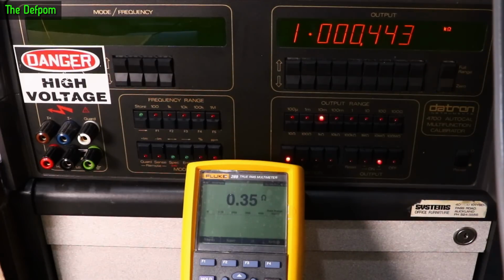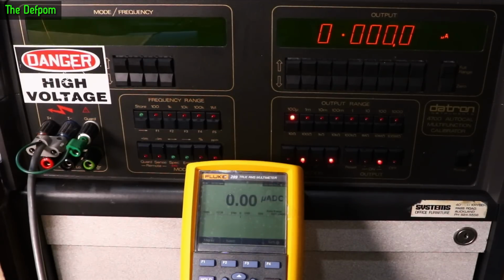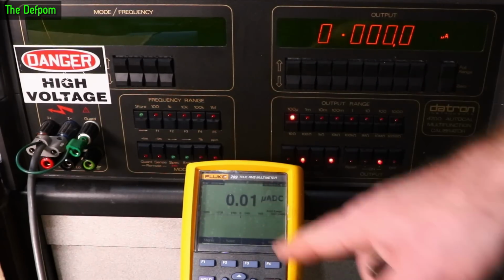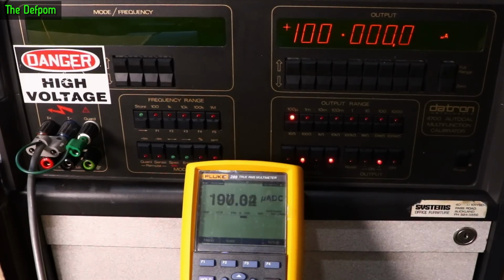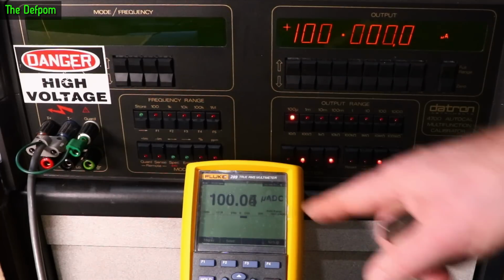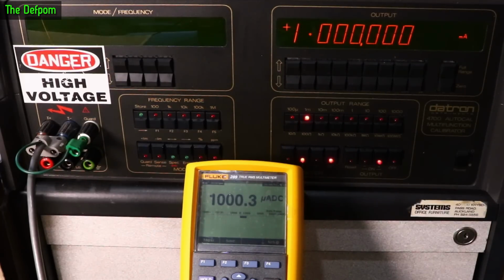And I've got a short here is 0.175, and that's 0.35. So it's very slightly better than this calibrator does for a short. Not much in it though. It's all good. Now let's do microamps DC. Got the output 0. We're getting 0. Still 100 microamps. It's pretty good. 5 counts out. 1000 microamps, or 1 milliamp. That's 3 counts out. That's alright.